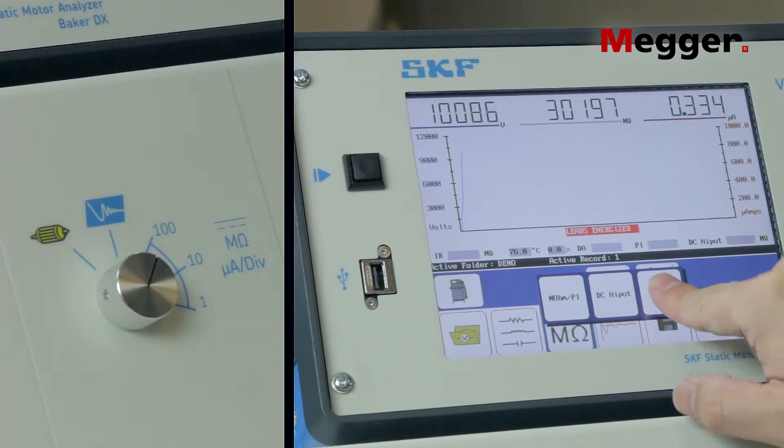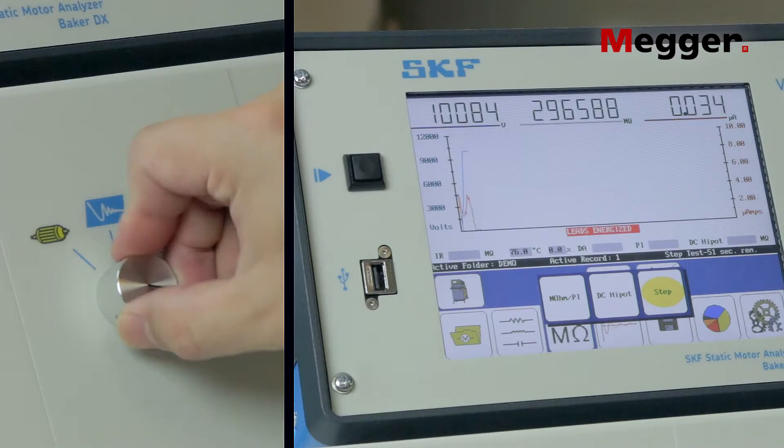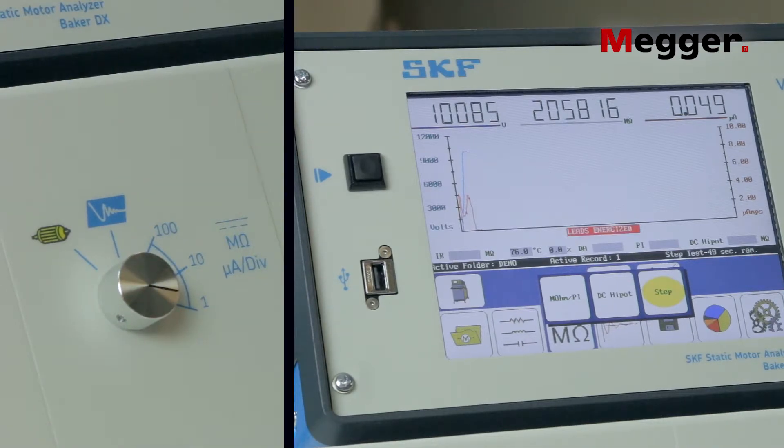Press the step button to initiate the step timer, which by default will be one minute long. While the voltage is held at a constant value, the leakage current will diminish over time. If the current value falls below half of the lowest division, turn the power pack's function knob to 10 microamps per division.